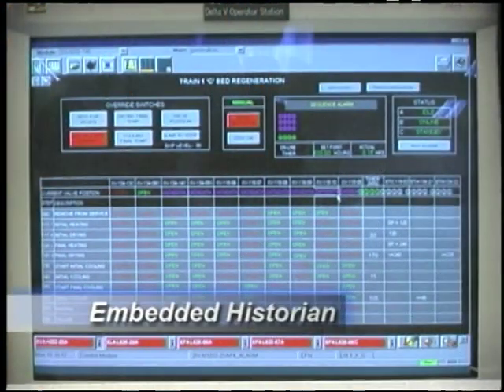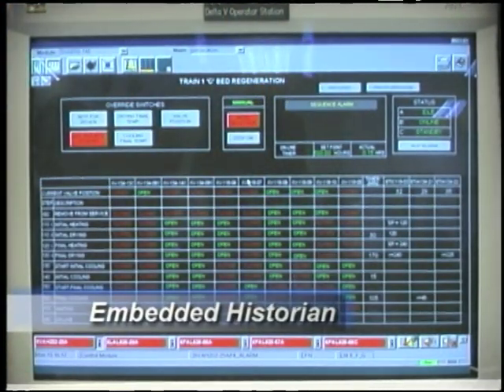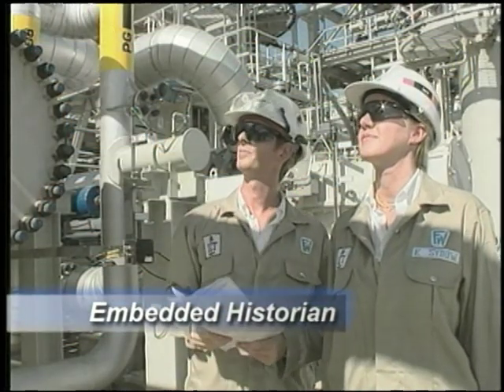In order to achieve that, we have to get the information from the field, which is why we went for Foundation Field Bus. The system's embedded historian lets Shell keep tighter control of its operations and delegate maintenance to its suppliers. Both the platform and the onshore gas plant have their own historians, and there's also a central historian based on the onshore gas plant. We store a large amount of information on the historian, used for trending, and we also access that information on a web server. That's a big benefit - the trending of information, to go back after an event to see how it reacted, what improvements we can make, and it gives us a good history. Very useful, especially if you're monitoring a critical parameter.